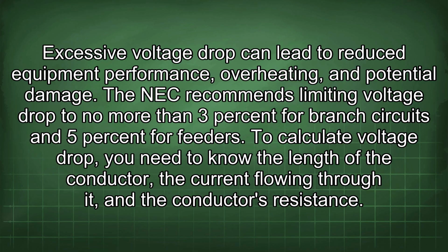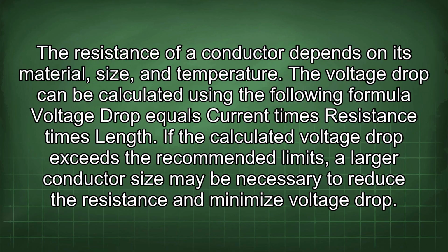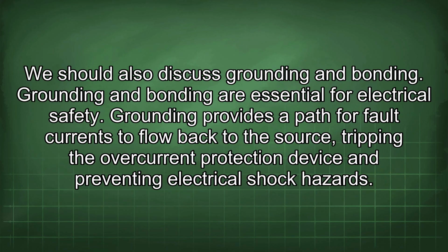To calculate voltage drop, you need to know the length of the conductor, the current flowing through it, and the conductor's resistance. The resistance of a conductor depends on its material, size, and temperature. The voltage drop can be calculated using the following formula: voltage drop equals current times resistance times length. If the calculated voltage drop exceeds the recommended limits, a larger conductor size may be necessary to reduce the resistance and minimize voltage drop. We should also discuss grounding and bonding.